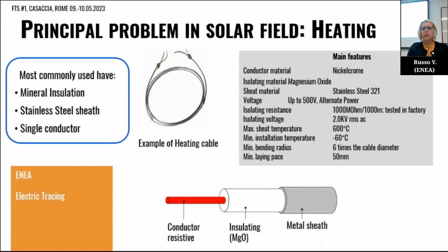For what concerns the electric tracing, here is a picture of a common heating cable. Generally, the cables have a mineral insulation, a stainless steel sheath, and a single conductor. Here in this table are summarized the main features of the cable used in a solar plant. Generally the conductor material is nickel chrome, the insulating material is magnesium oxide, the maximum temperature allowed is 600 degrees, and so on. Here is the scheme of the cable, and it's possible to note the resistive conductor, the insulation, and the metal sheath.